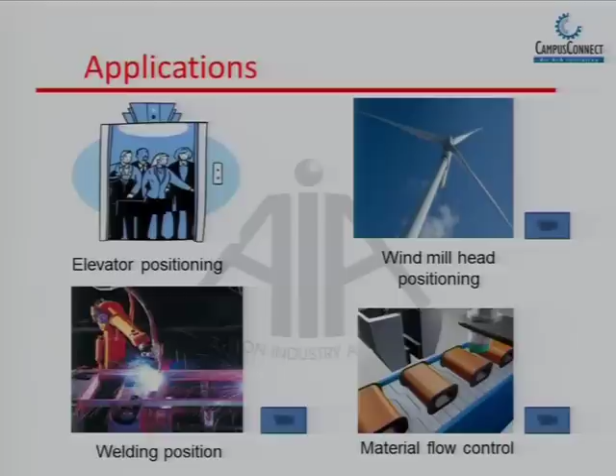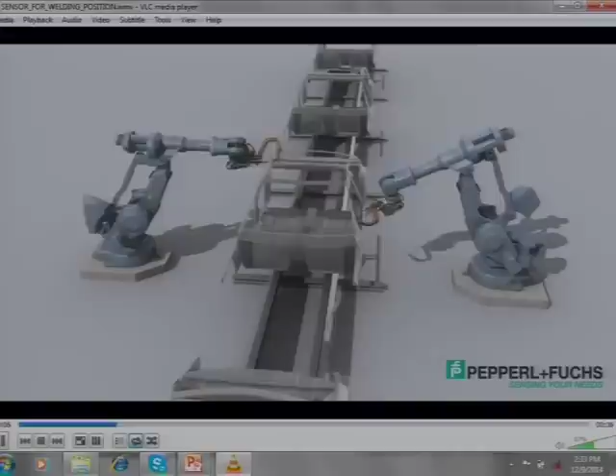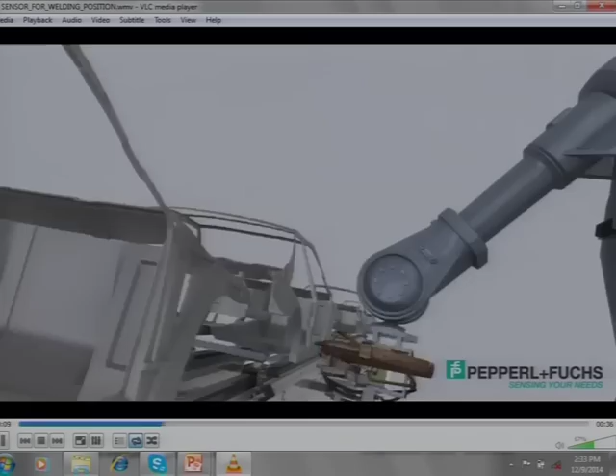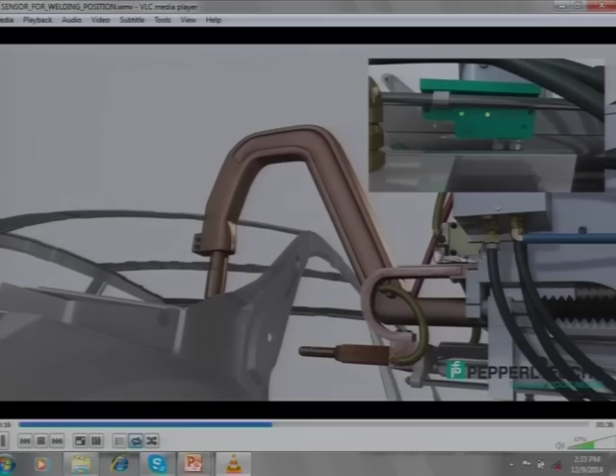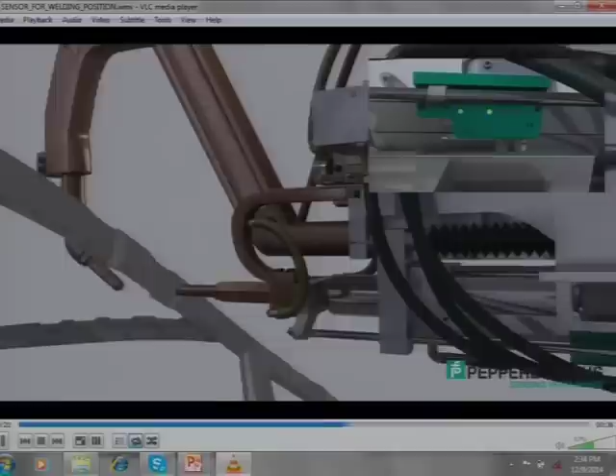Then there are certain sensors like weld immune sensors. Welding, as we all know, produces a lot of noise, and this noise interferes with the control signal. These sensors are designed so that they can withstand welding splatters. I just have a video of this. These sensors can withstand welding splatters because the EMI, electromagnetic interference, produced during the welding application is quite high, so they have to sustain that. Plus the body of the sensor is designed so that it will withstand the splatters. That means the splatters will not get stuck onto the sensing head and will not damage the sensor. These sensors are known as weld immune sensors. They are immune to welding applications.